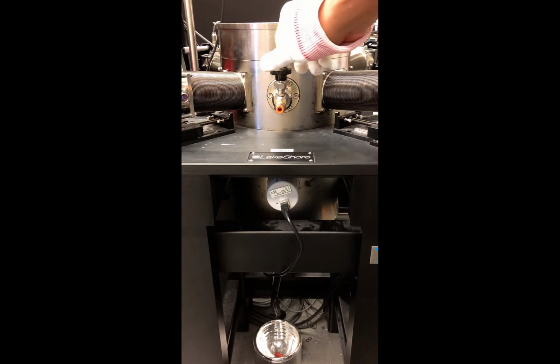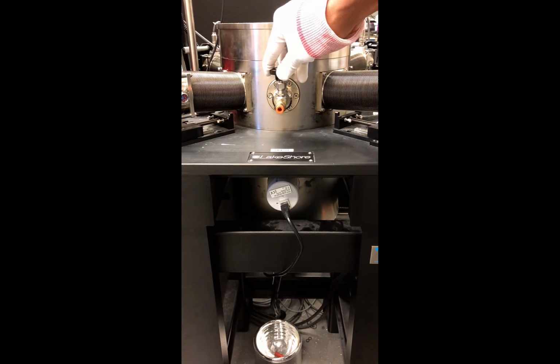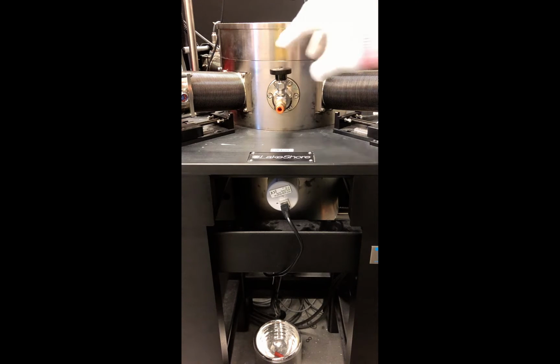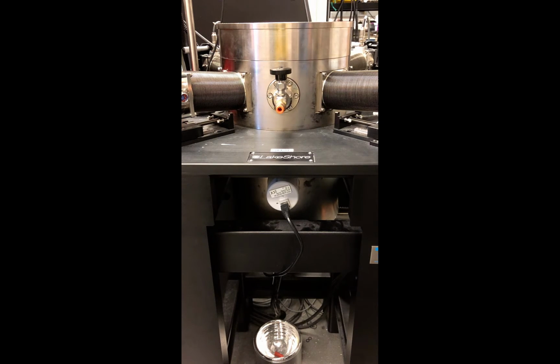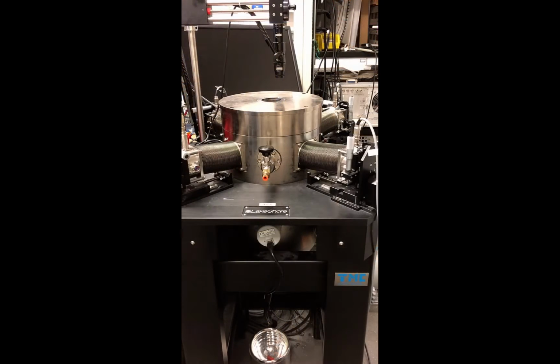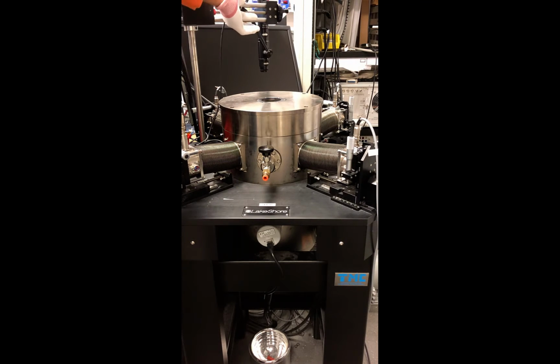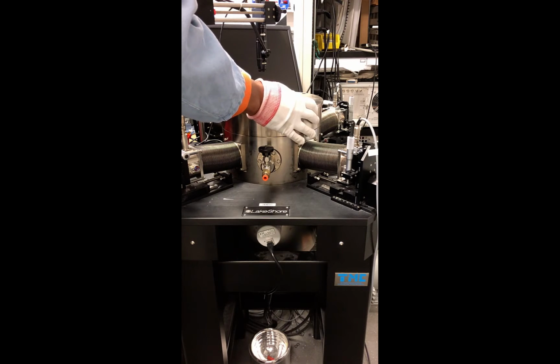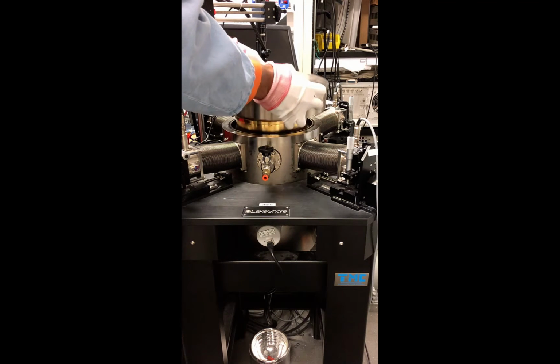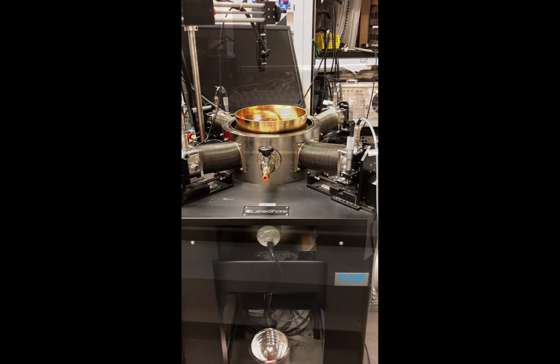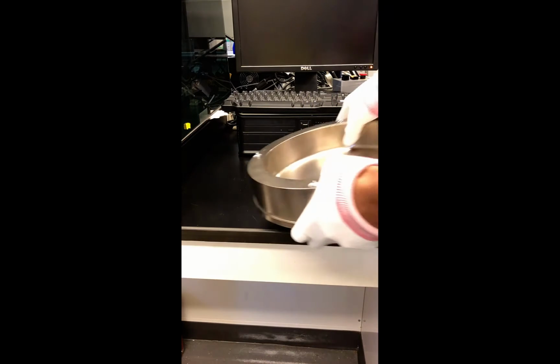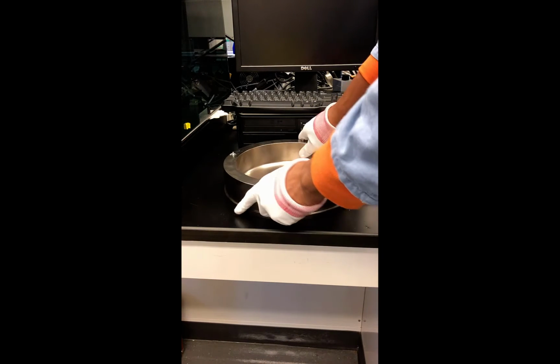Then you can vent the sample chamber. Again, you'll be able to hear the chamber vent when you turn the black knob. Please follow this order of turbo pump first and sample chamber second, as it helps to keep the turbo pump blades balanced. Once the sample chamber is vented, you can remove the lid and place it to the side. We normally just find a countertop nearby to hold the lid while we continue our setup.